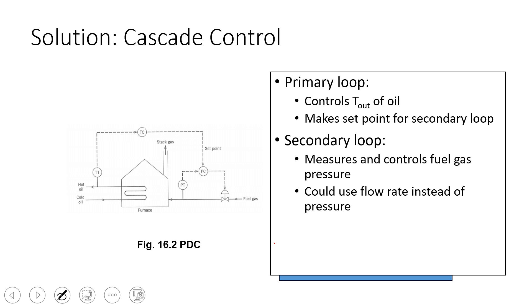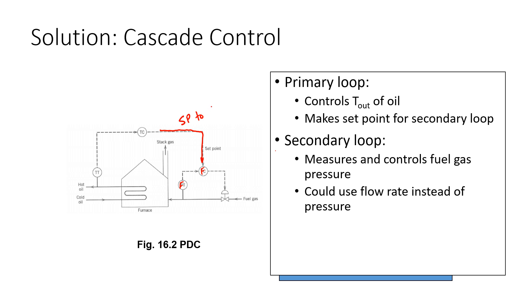One solution is cascade control for this. If we want to measure pressure right here — this could also be a flow controller. For example, if I just change this to an FT and an FC, install a flow transmitter and flow meter there, and then have a flow controller, that might be more common than a pressure one. The primary loop consists of the temperature out of the oil, and this makes a set point for the secondary loop. The secondary loop measures and controls the fuel gas pressure. This is going to be a set point to the secondary.